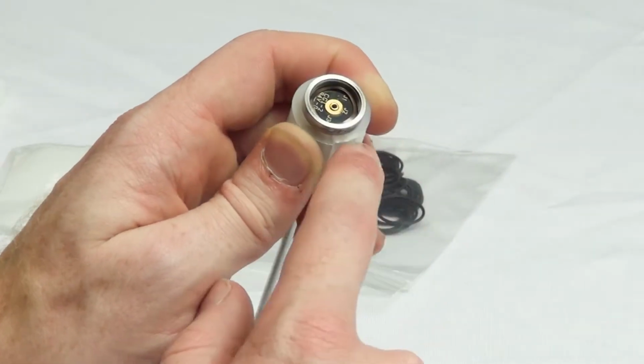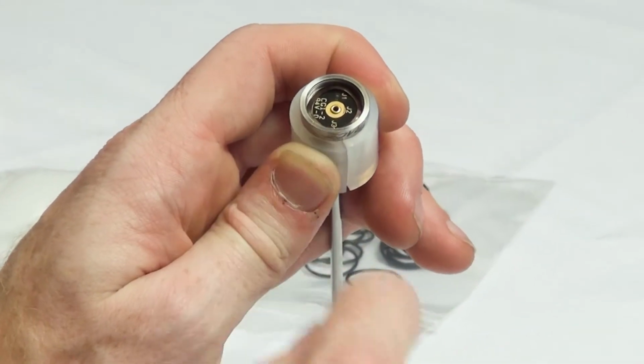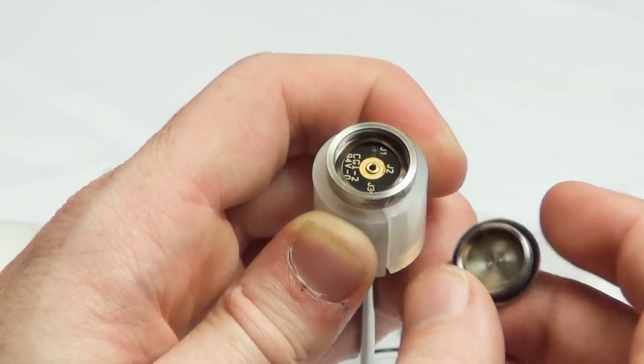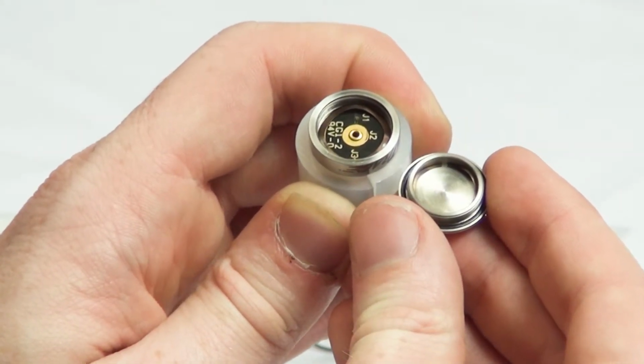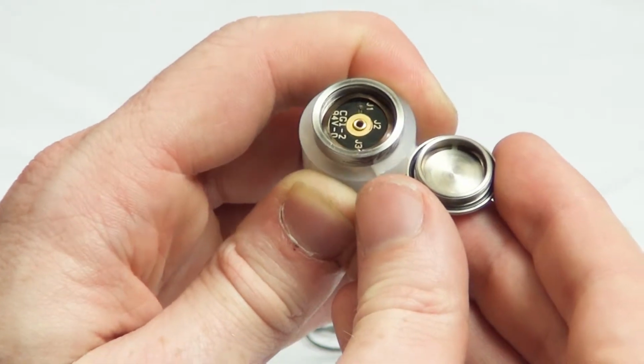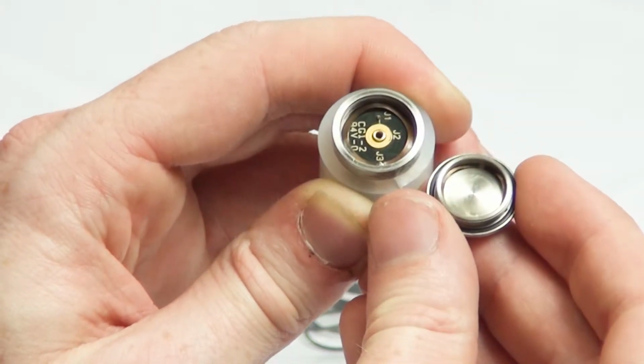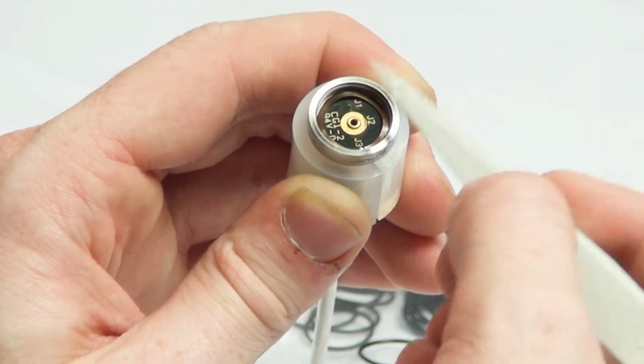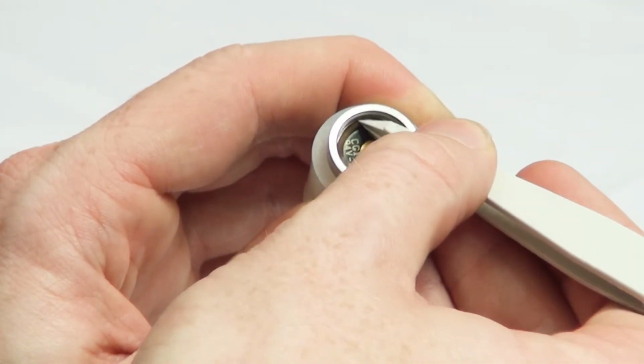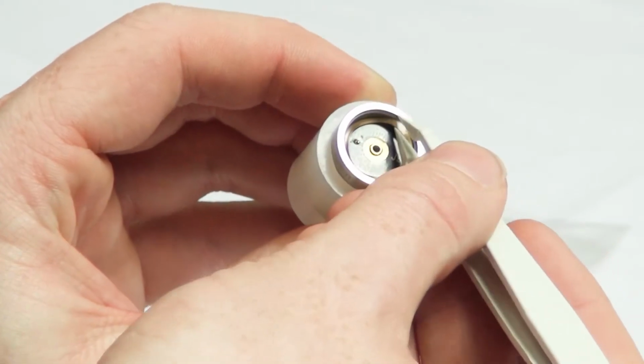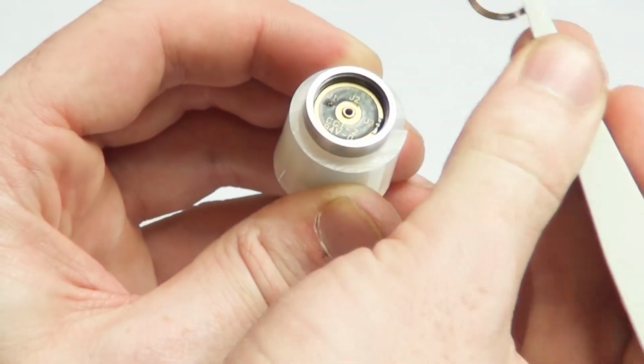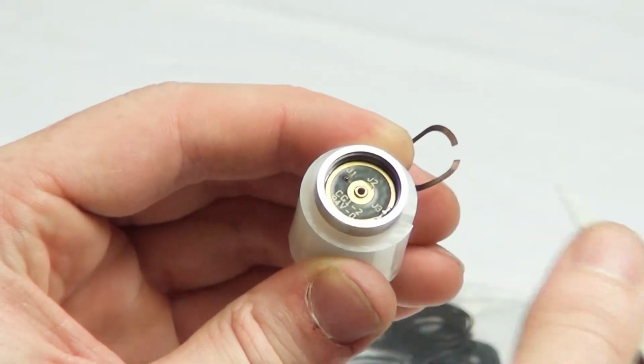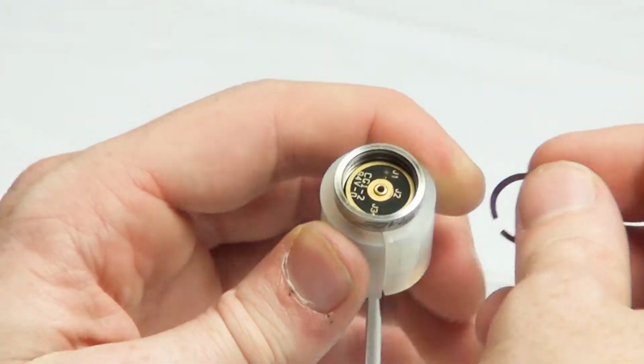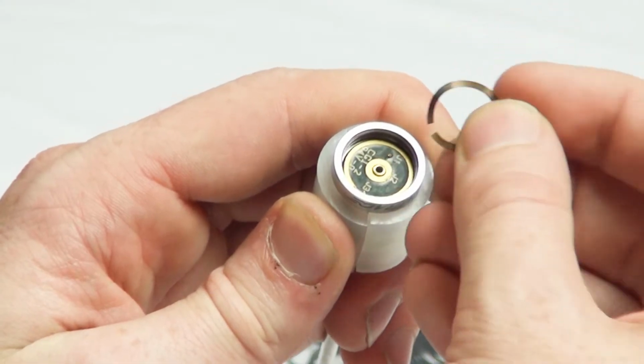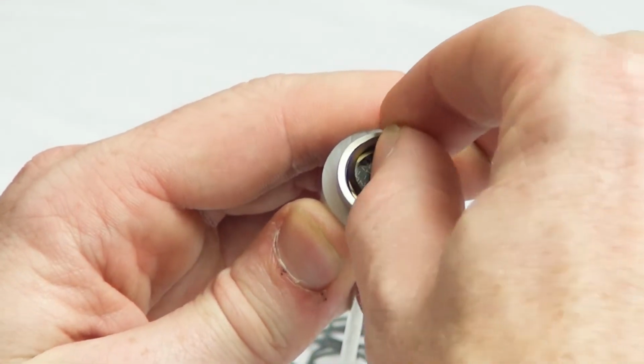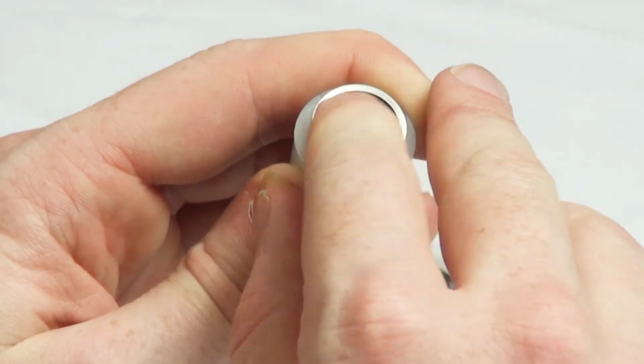Examine the battery compartment here in the logger and the cap, making sure that the wave springs are located correctly inside, and if one of the springs has fallen out, reinsert it. These springs are removable, and to reinsert, just take the spring, open-ended, facing down, and push it back in with your finger.